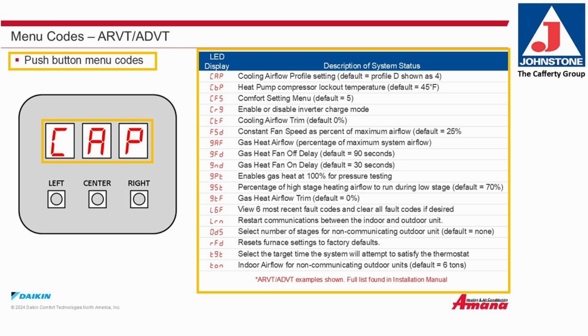L6F, view the 6 most recent fault codes and clear all fault codes if desired. LRN, restart communication between the indoor and outdoor unit. ODS, select the number of stages for non-communicating outdoor unit. Default, none. RFD, reset furnace settings to factory default. TGT, select the target time the system will attempt to satisfy the thermostat. TON, indoor airflow for non-communicating outdoor unit. Default 6 tons. These are ARVT, ADVT examples that are shown. For the full list, please consult the installation manual.